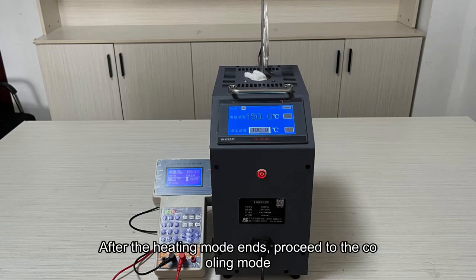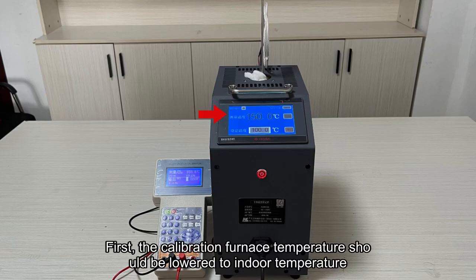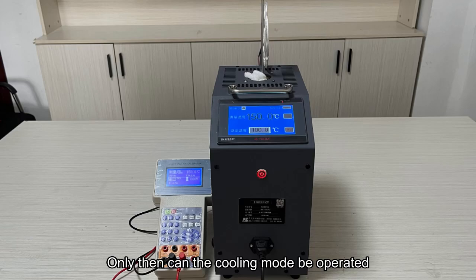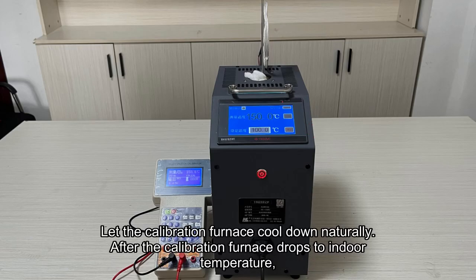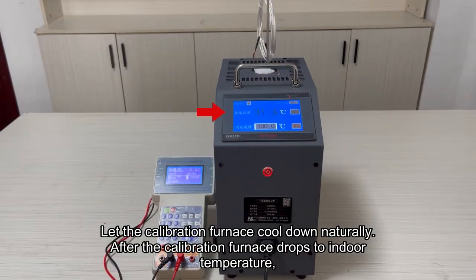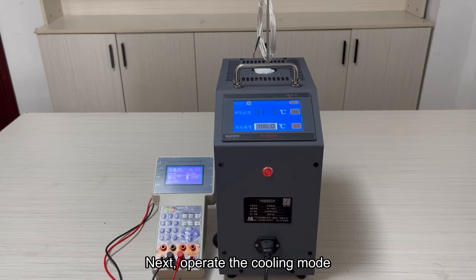After the heating mode ends, proceed to the cooling mode. First, the calibration furnace temperature should be lowered to indoor temperature. Only then can the cooling mode be operated. So click the Stop button first. Let the calibration furnace cool down naturally. After the calibration furnace drops to indoor temperature. Next, operate the cooling mode.